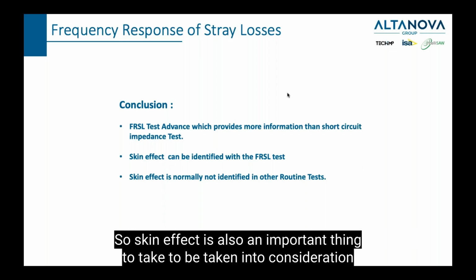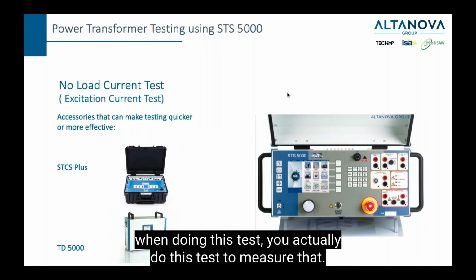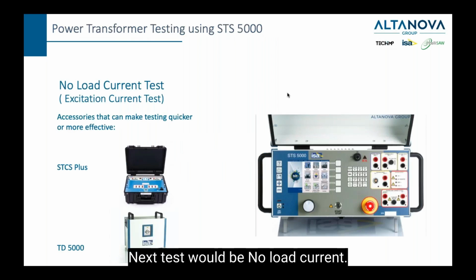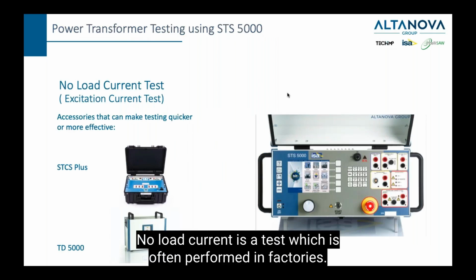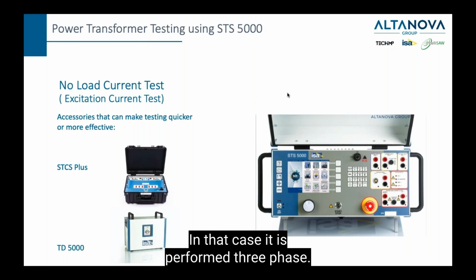So skin effect is also an important thing to be taken into consideration when doing this test. You actually do this test to measure that. Next test would be no load current. No load current is a test which is often performed in factories. In that case, it is performed three-phase.